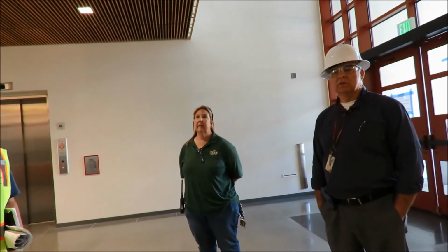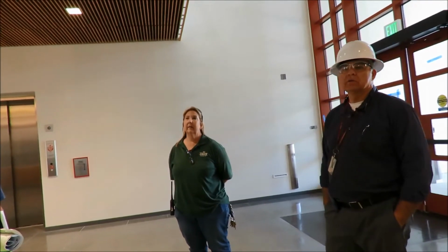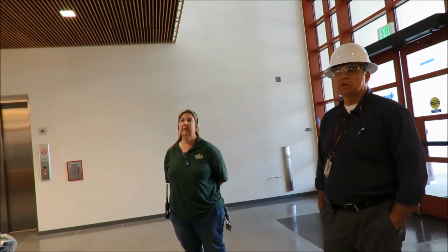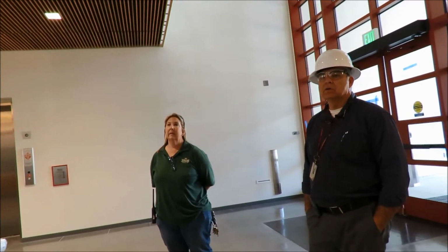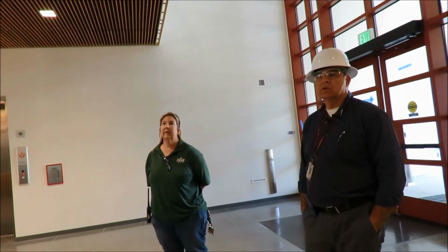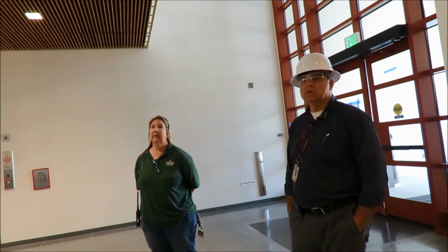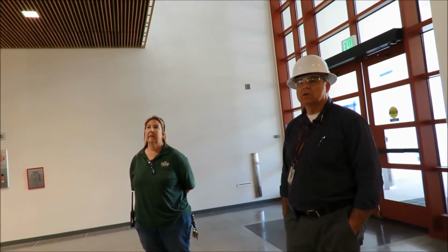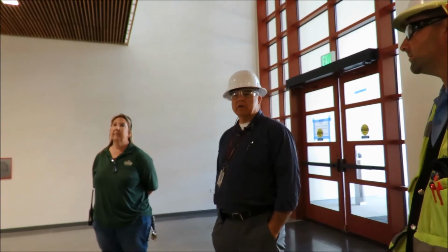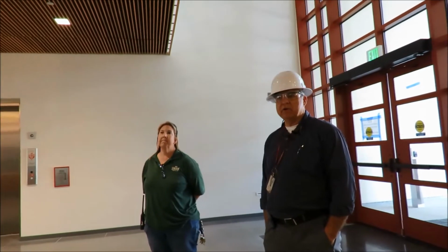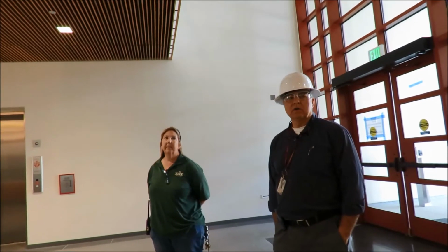Yeah, I think that's what the shunt trip we have up there is for. It takes it to whatever floor the fire alarm or smoke detector has not activated, where it feels it's safe to let the people out, opens the doors, and then trips the breaker with the shunt trip, and you can't use the elevator anymore. But in a power out, could it go through that sequence? Does it have enough? No, it doesn't. Power out, you're dead in the water. As soon as power goes out, it's dead.